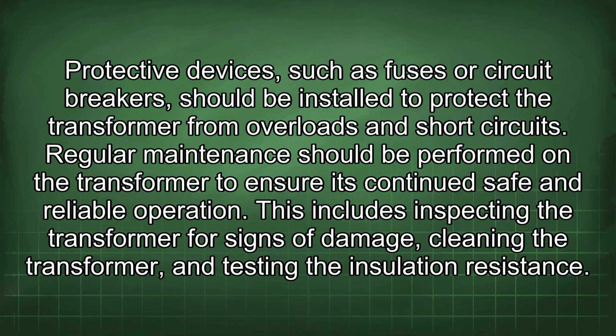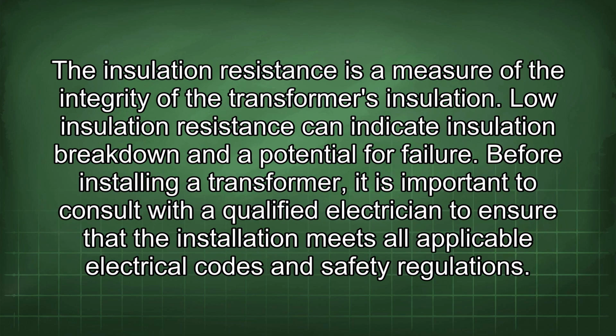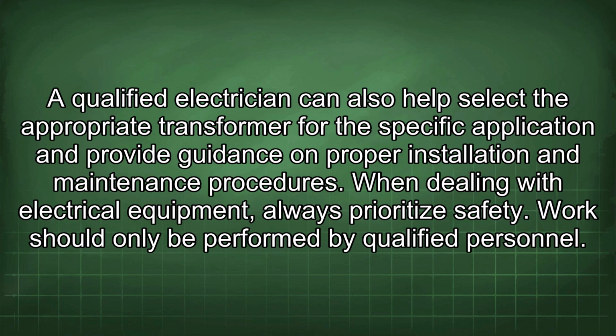Regular maintenance should be performed on the transformer to ensure its continued safe and reliable operation. This includes inspecting the transformer for signs of damage, cleaning the transformer, and testing the insulation resistance. The insulation resistance is a measure of the integrity of the transformer's insulation. Low insulation resistance can indicate insulation breakdown and a potential for failure. Before installing a transformer, it is important to consult with a qualified electrician to ensure that the installation meets all applicable electrical codes and safety regulations. A qualified electrician can also help select the appropriate transformer for the specific application and provide guidance on proper installation and maintenance procedures. When dealing with electrical equipment, always prioritize safety.